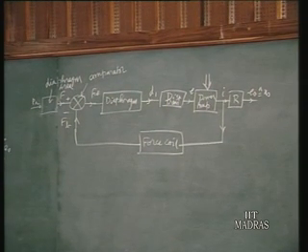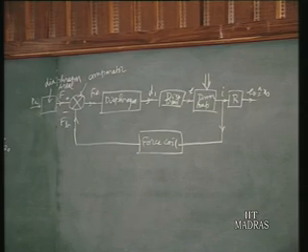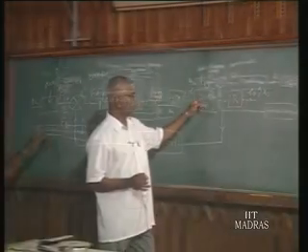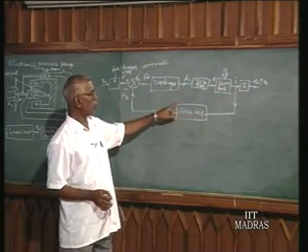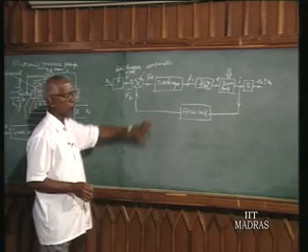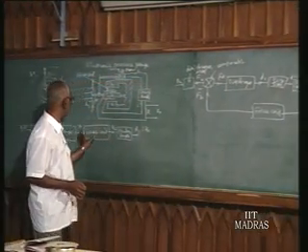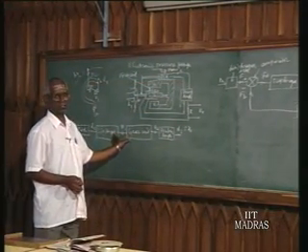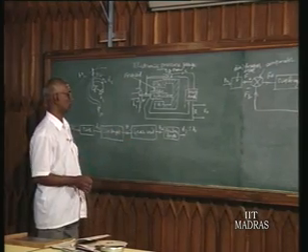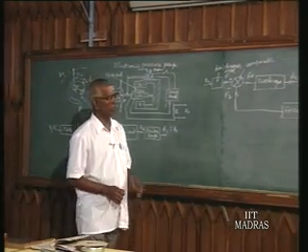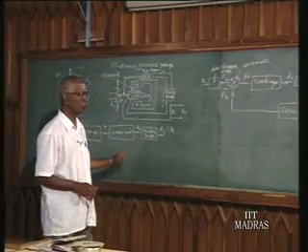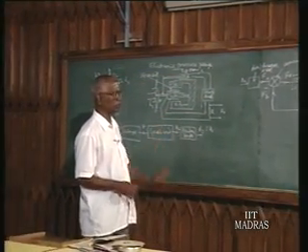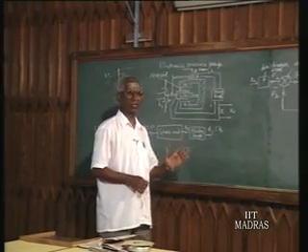Now what is the difference between the signal flow diagram of the electronic pressure gauge and the Bourdon pressure gauge? Here the signal flow diagram is straight, whereas in the electronic gauge there is a loop in the signal flow diagram. Hence we call it an instrument based upon closed loop condition, and the Bourdon pressure gauge is an instrument based upon open loop. This way also the whole field of instruments is divided: instruments working in closed loop and instruments working in open loop condition. What is the advantage and disadvantage of these two setups?